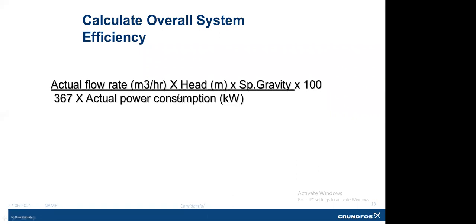And we need to divide this hydraulic power by the actual power consumption, and it gives us the system efficiency of the pump. If we use the pump input power, it will give us the pump efficiency. But practically, we cannot measure the pump input power, that is the motor output. We always measure the overall pump plus motor efficiency by measuring the motor input power.